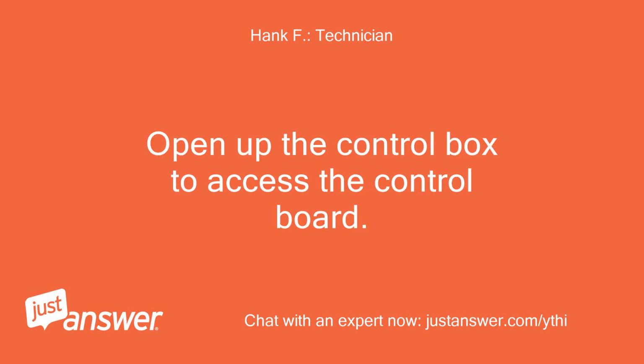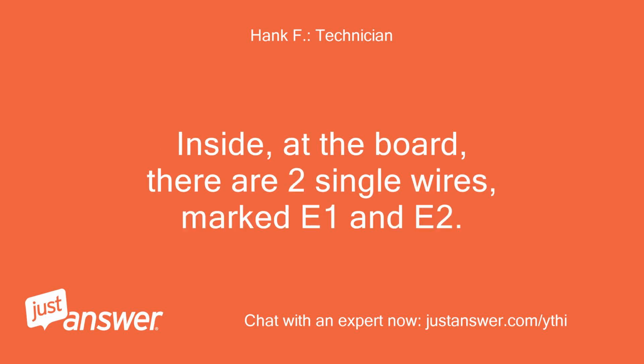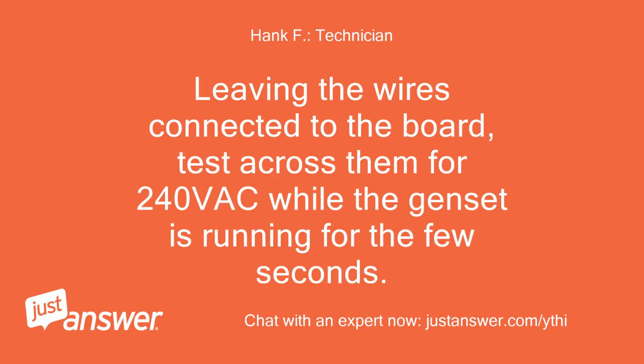Open up the control box to access the control board. Inside, at the board, there are two single wires, marked E1 and E2. Leaving the wires connected to the board, test across them for 240 VAC while the genset is running for a few seconds.